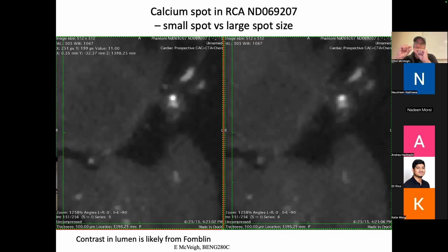So now, instead of a small spot size, it opens the spot size up, and the electrons hit a bigger target to make more X-rays. And so, if you wanted to go to a higher fluence of X-rays, you would be over here going higher, and the spot size would remain large.